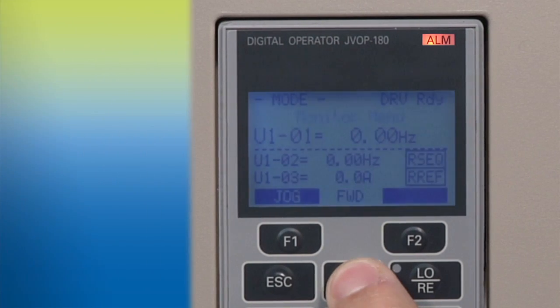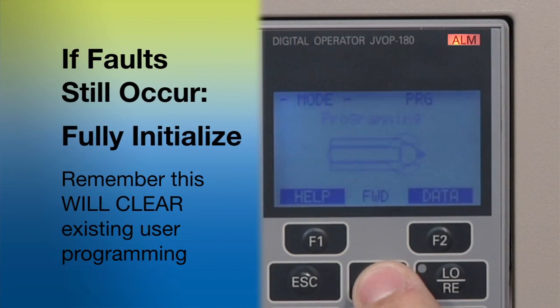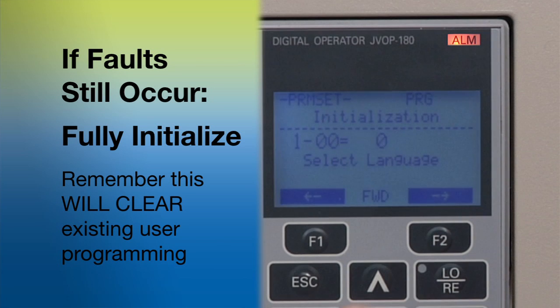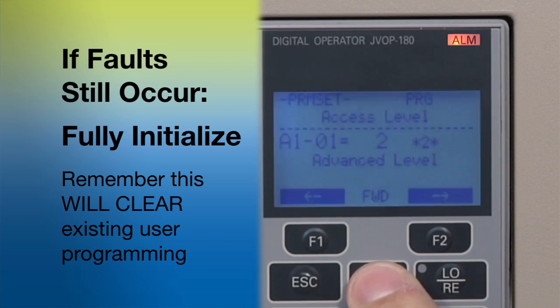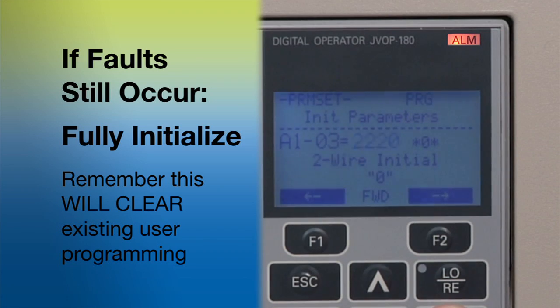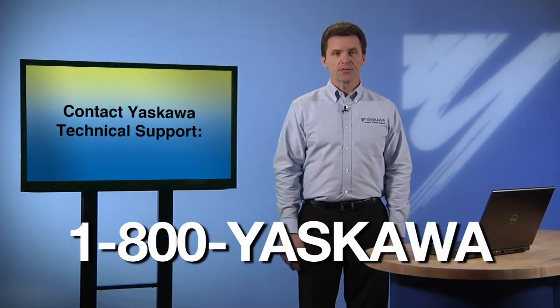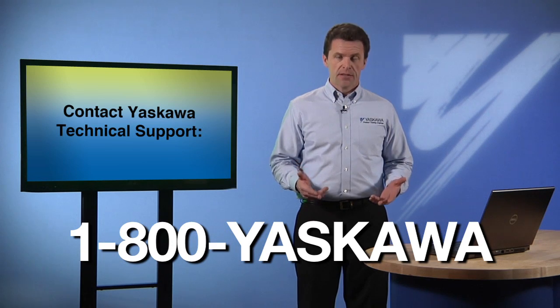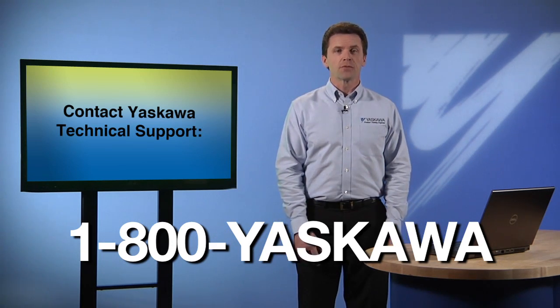Now, if you're still getting alarms or faults, try reinitializing the drive. But before you do, remember that reinitializing will clear out the drive's current programming. On the other hand, reinitializing the drive should remove most alarms and faults. If problems still persist, or if the keypad is locked out, contact Yaskawa Technical Support for further troubleshooting measures.